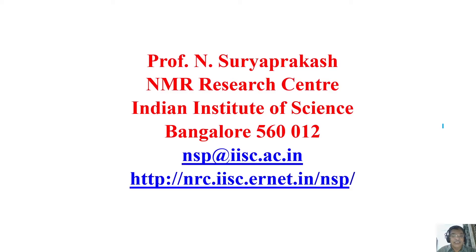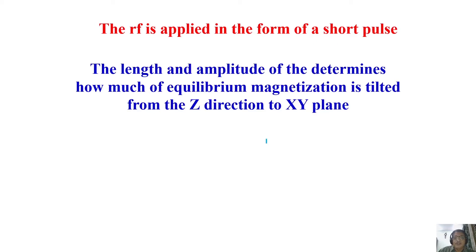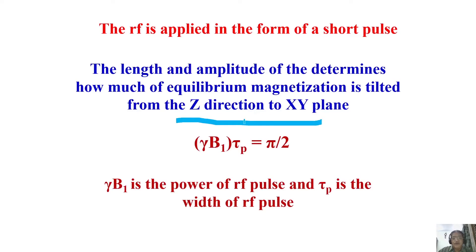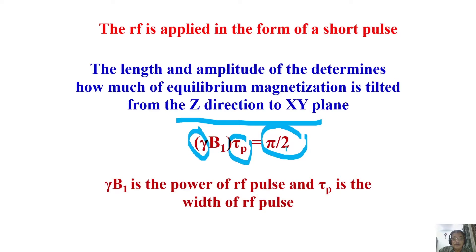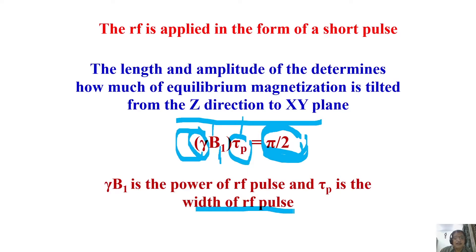You can manipulate the amount of magnetization tilted in different directions by applying radio frequency pulses in different directions. The pulse is applied as a short RF burst, and you can adjust RF power and pulse width to get the desired flip angle. Gamma B1 gives the pulse power. Knowing gamma, pulse width, and pi by 2, you can play with RF power and pulse duration to tilt the magnetization by any desired amount.